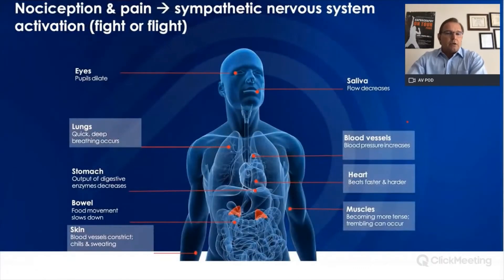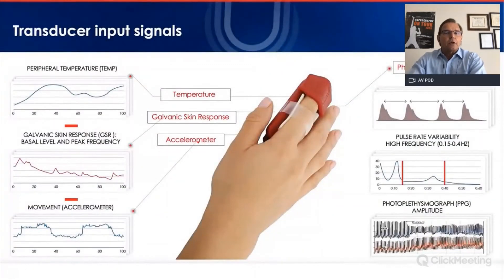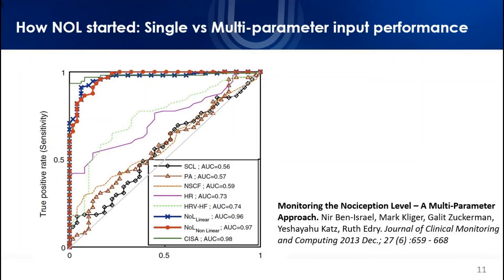Pain and nociception both activate the sympathetic nervous system: pupils dilate, breathing and heart rate increase, blood vessels constrict, sweating occurs, and parasympathetic functions such as gut motility and digestive enzyme secretion are turned down. NOL captures signals from several of these sympathetically activated organ systems. The NOL transducer looks like a bulky pulse oximeter — I call it the Tesla of index finger transducers because it does a lot of cool things. It measures photoplethysmography, galvanic skin response (skin conductance as it changes when the body sweats), and has an accelerometer.